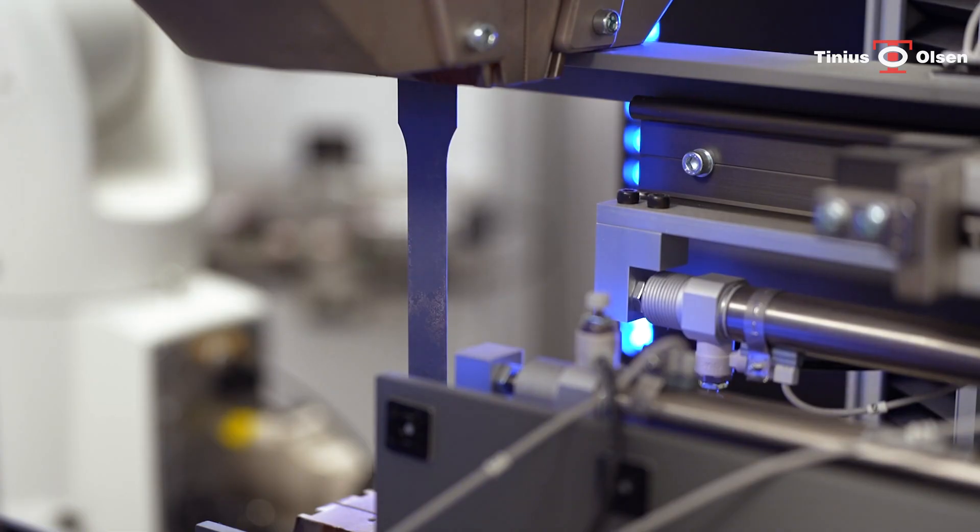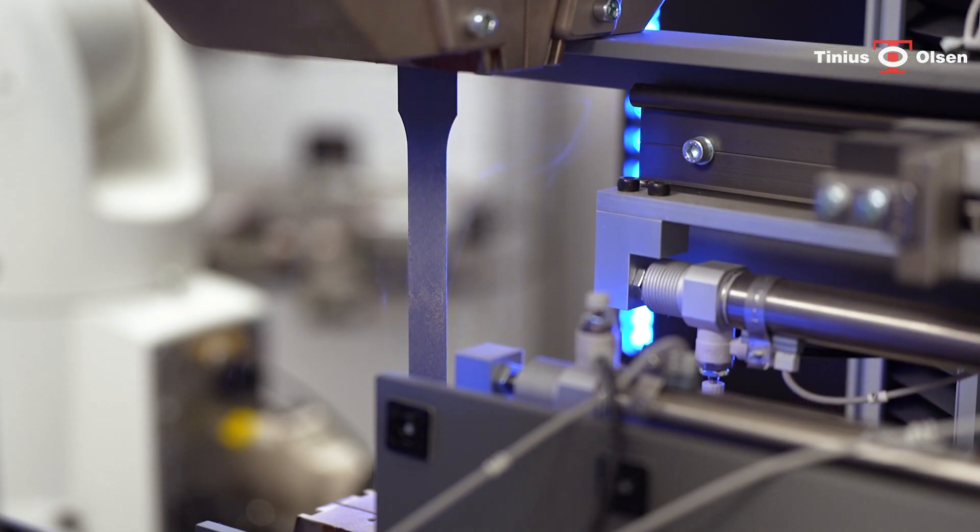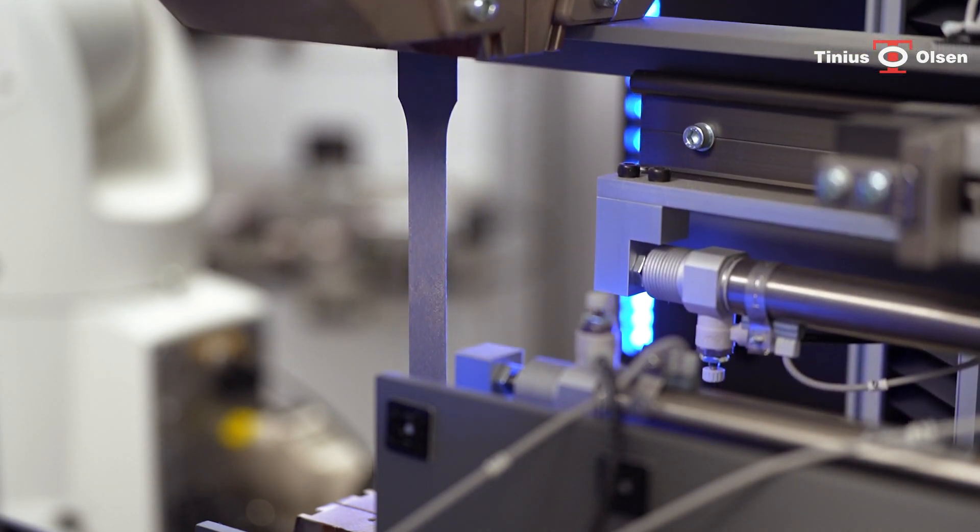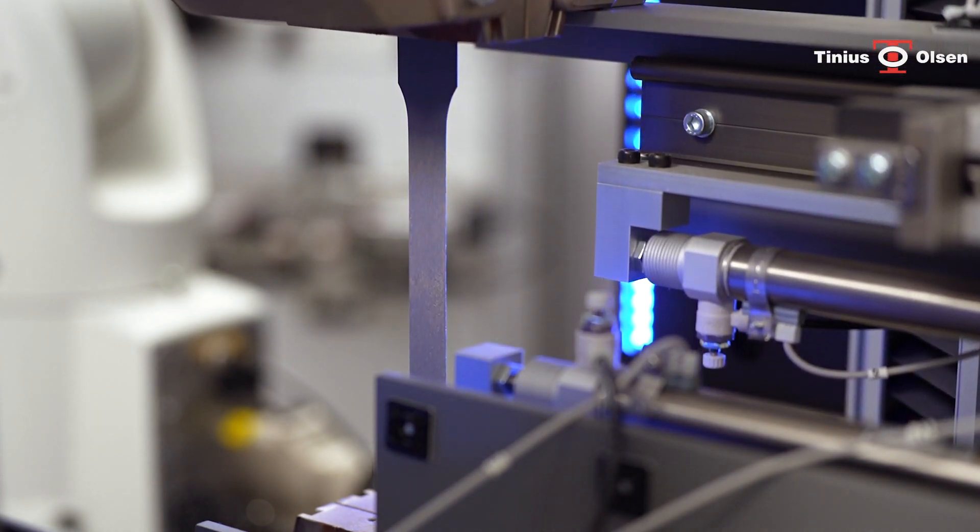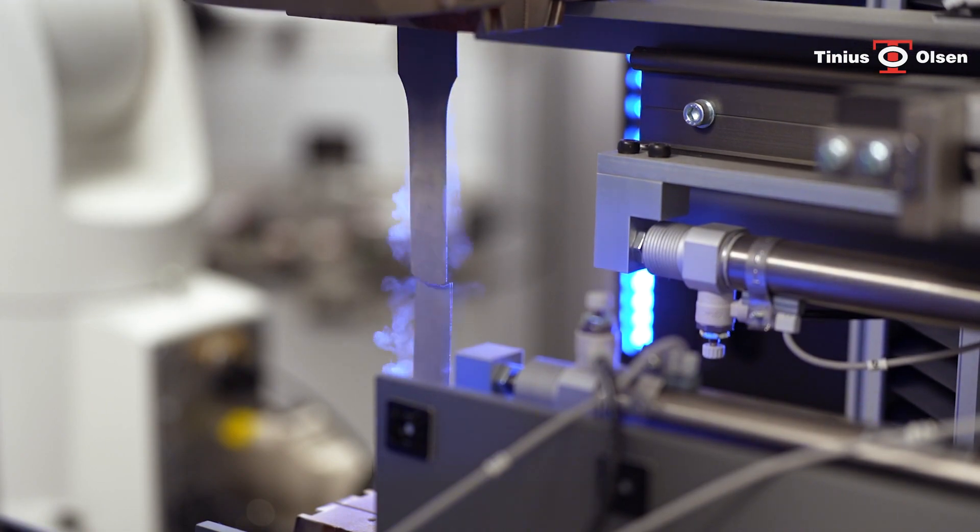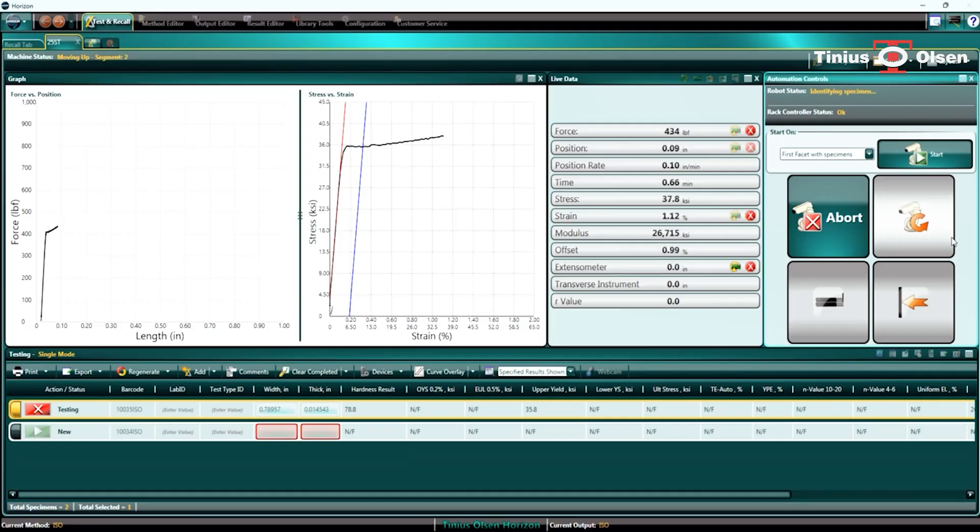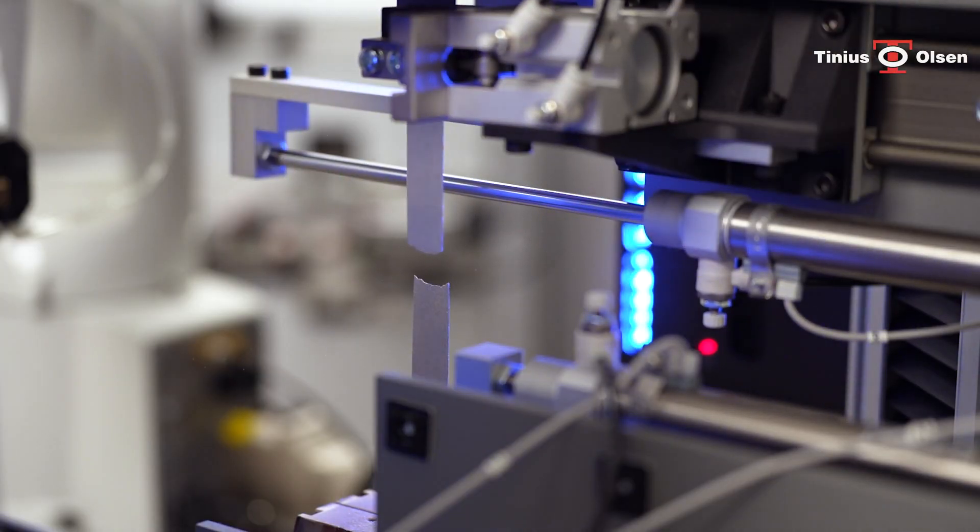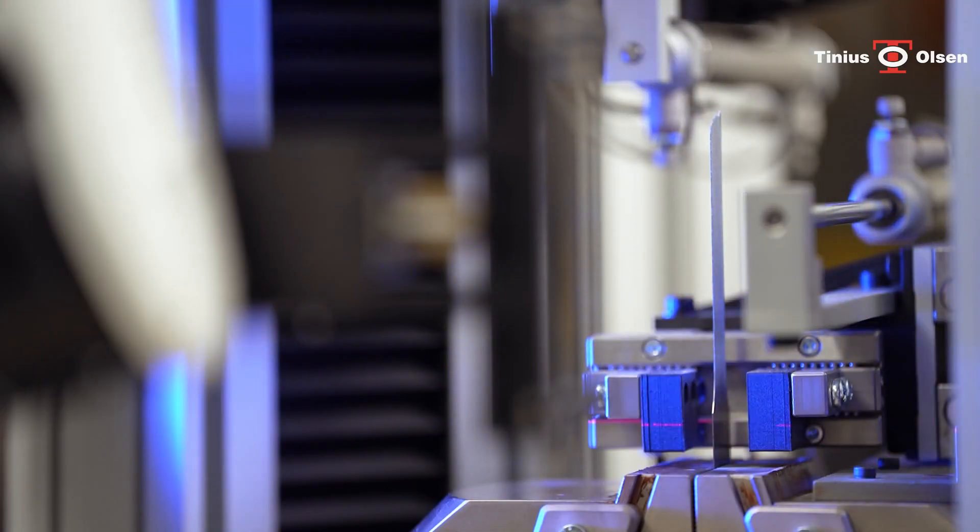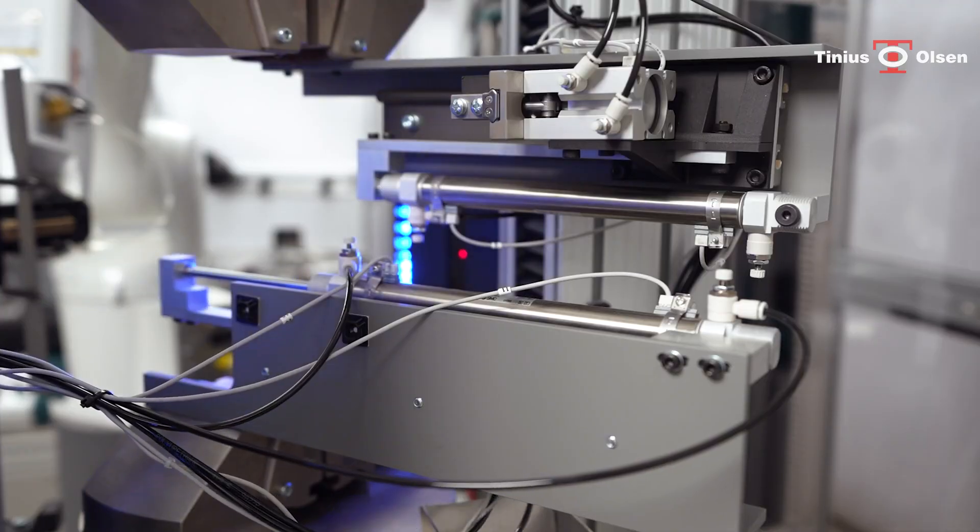The universal testing system will perform the test in strict accordance with ASTM or ISO standards. Once the specimen ruptures and the test concludes, the pneumatic specimen removal system on the 25 ST will automatically eject and discard the specimen into the designated bin behind the test frame.